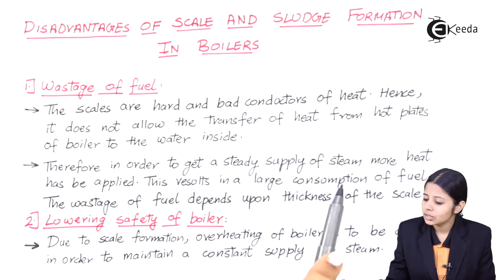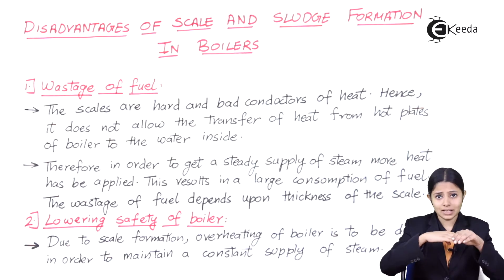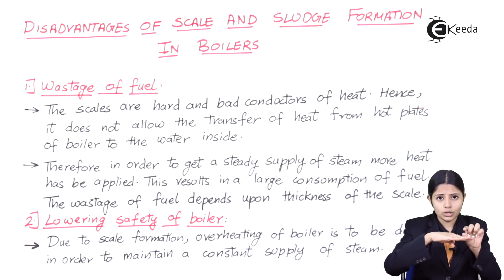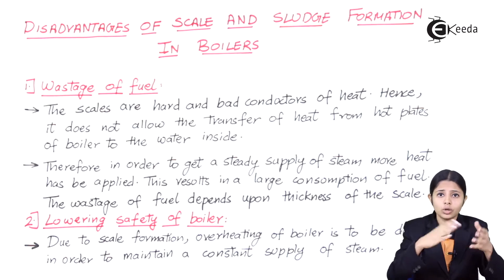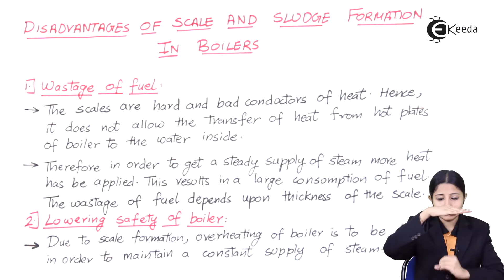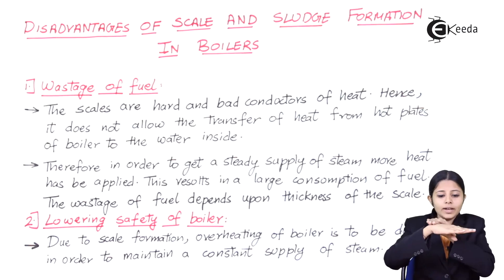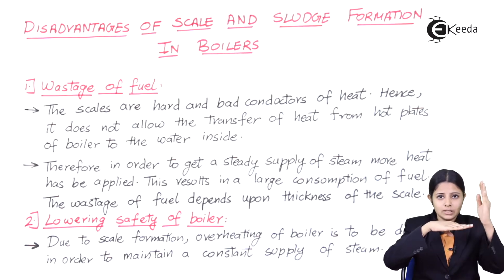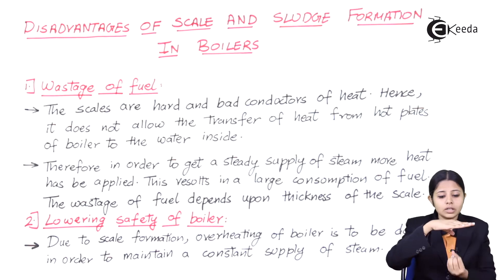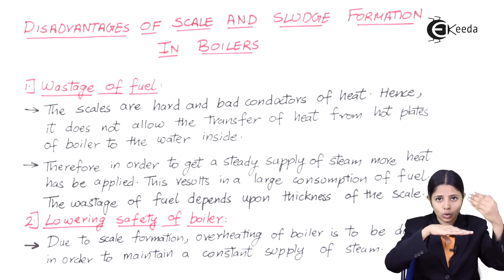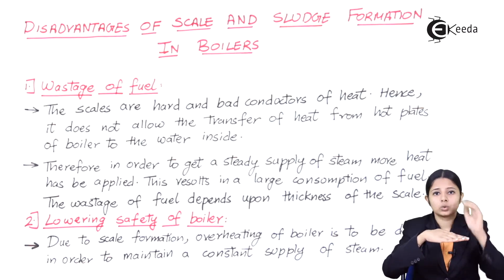Therefore, in order to get a steady supply of steam, more heat has to be applied, resulting in large consumption of fuel. The wastage of fuel depends upon the thickness of the scale. Scale is a hard layer of impurities and earth particles from hard water that has settled in the boiler. If the scale layer is thin, heat passes easily; but if the scale is thick, heat is trapped and the water above does not get boiled, requiring even more fuel.